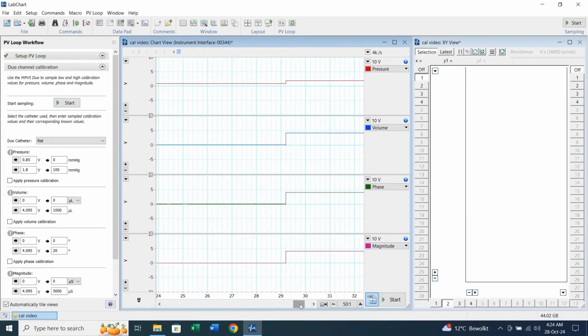Now for the pressure channel, select the region of LabChart just before and then just after where you can see the data jumped when the high calibration data was recorded. Add these to the pressure calibration boxes, one for 0 mmHg and one for 100 mmHg, as demonstrated here. Repeat this for the remaining 3 channels. Do not forget to check the Apply Calibration checkbox for each. All 4 channels are now calibrated.